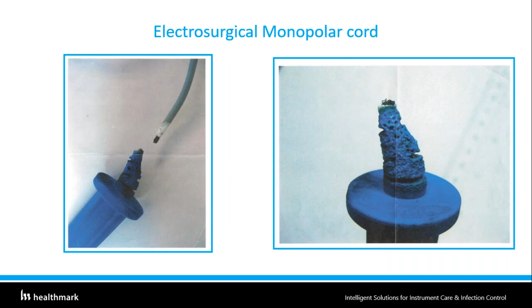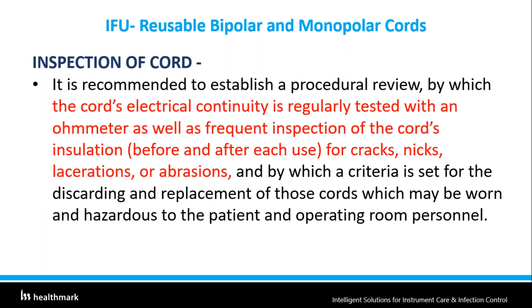If you look at the IFU for reusable bipolar and monopolar cords, it says that you need to check them every time you use them, using an ohm meter. But I have not seen a lot of ohm meters in the SPD department to check the continuity of these cords and make sure they are actually conducting electricity. Again, if you go back to the IFU, there is a warning that if you do not check these on a regular basis, you could cause a fire. Some of these are 10-use, some are 20-use. So if you don't have a system or mechanism to make sure you are using them according to the IFU, you could cause damage.